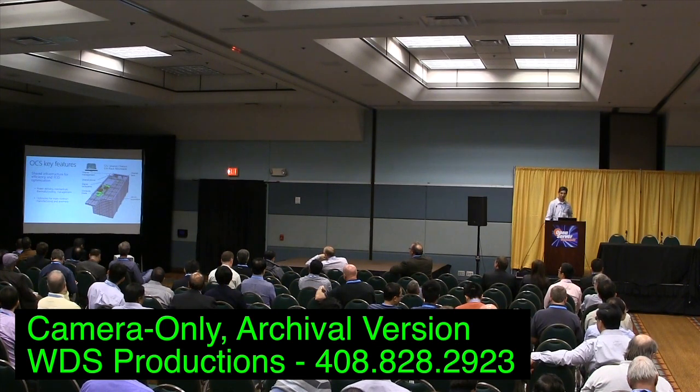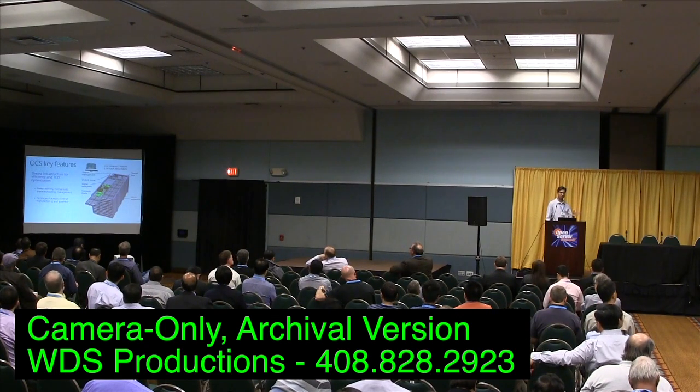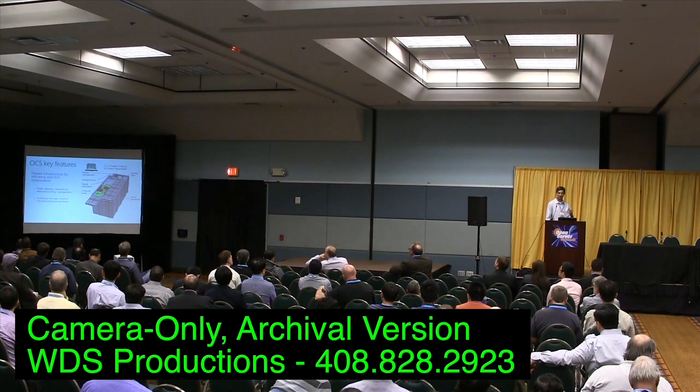So you see there is shared power. There are 6 power supplies in the back that deliver common 12-volt power. There is shared management. There is a chassis management card, and that removes a lot of the burden of the BMC, because the chassis manager becomes the front point for doing out-of-band access. There is a common shared signal backplane so that you can decouple the compute from the network, which is a key requirement, because network is evolving really fast.